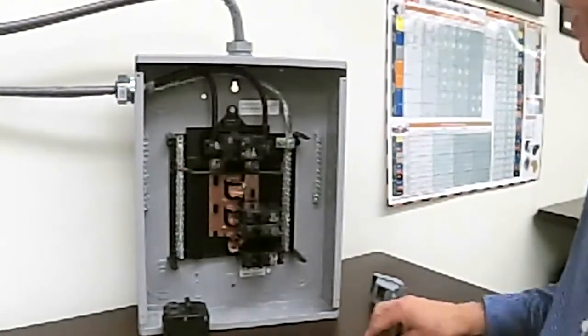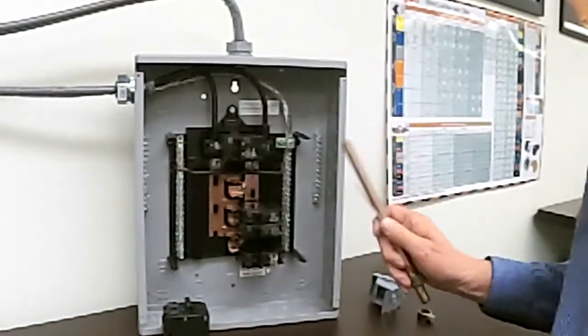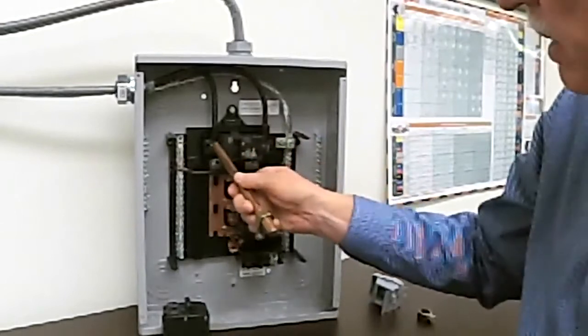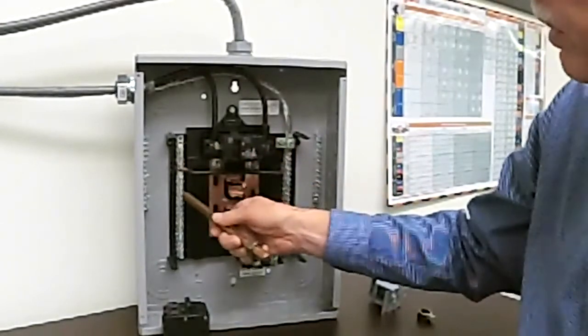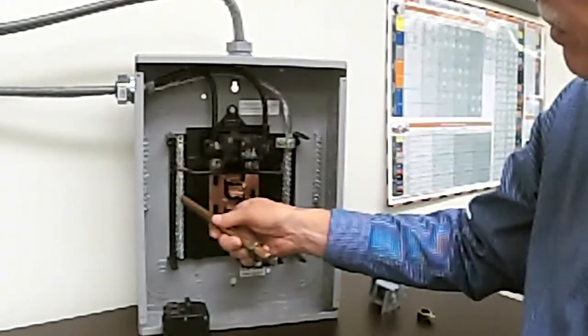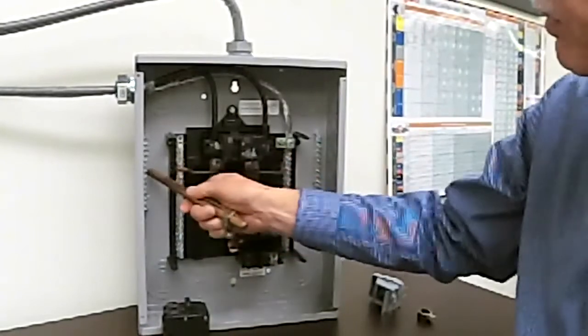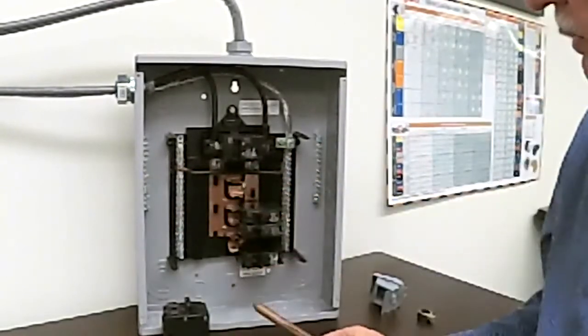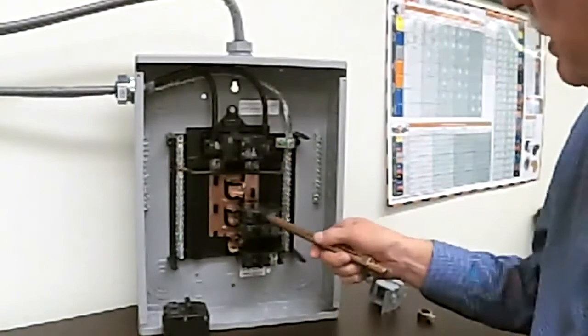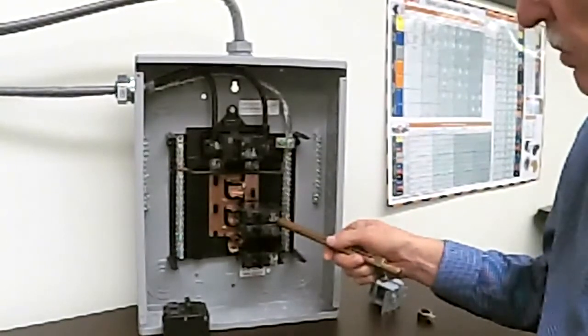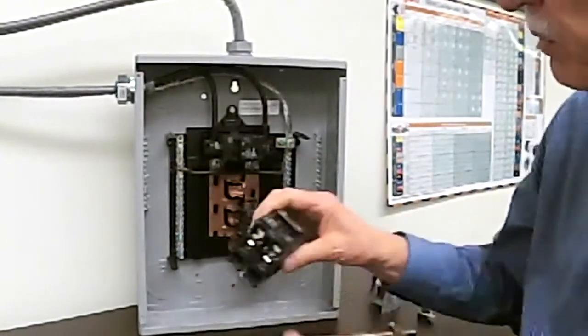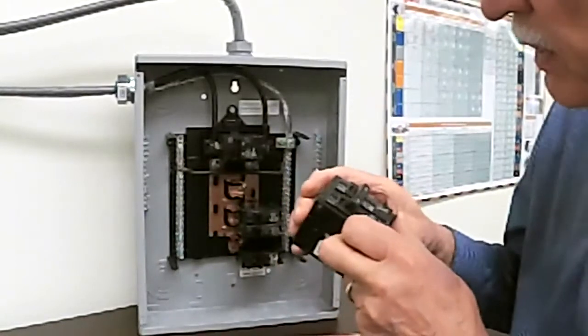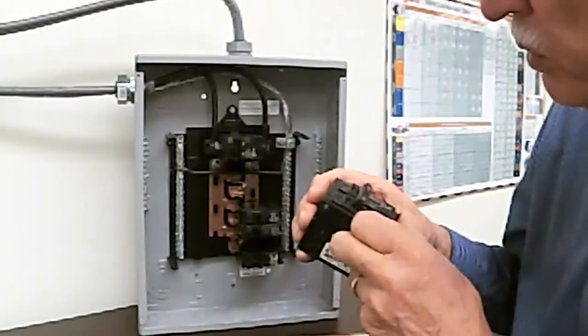I think that's it. Now, the torquing of these main lugs is different from the torquing for these neutral bar screws, is different from the ground bar screws, okay? And it's different from the circuit breaker requirement, okay?